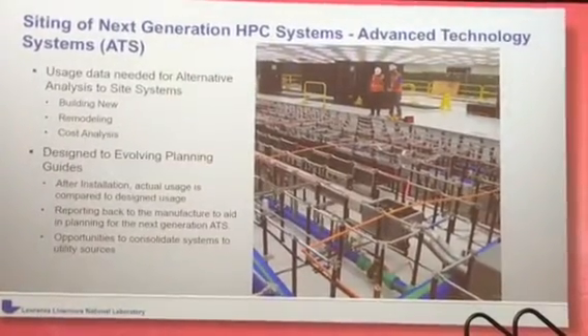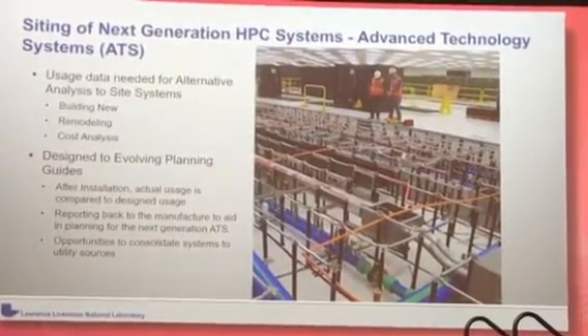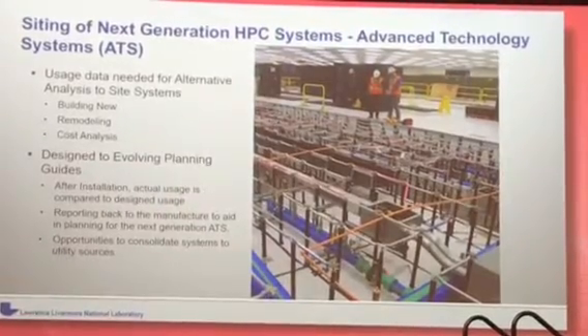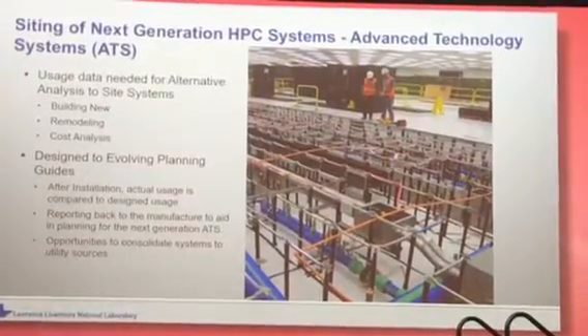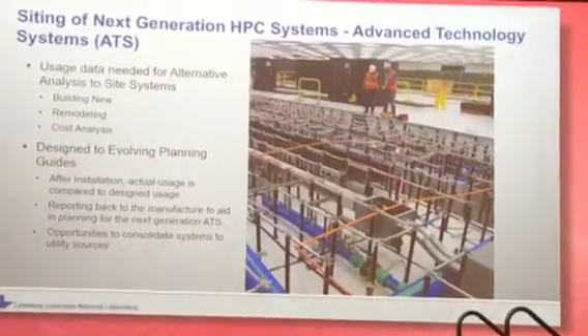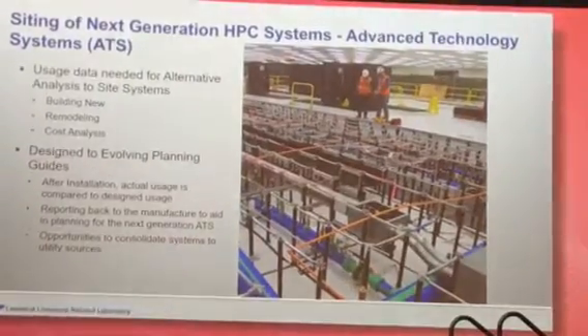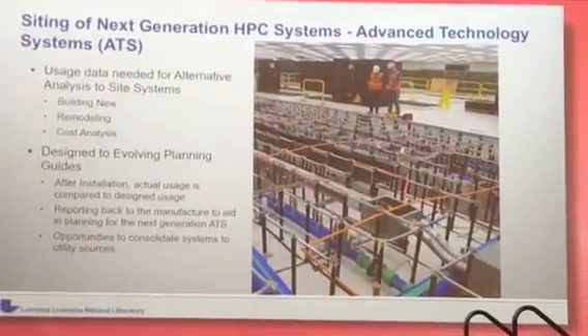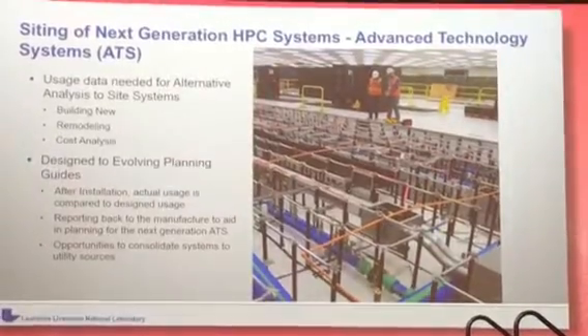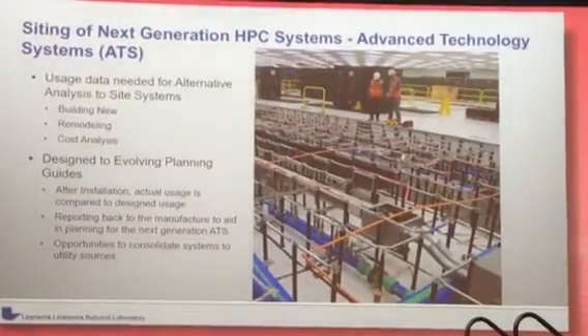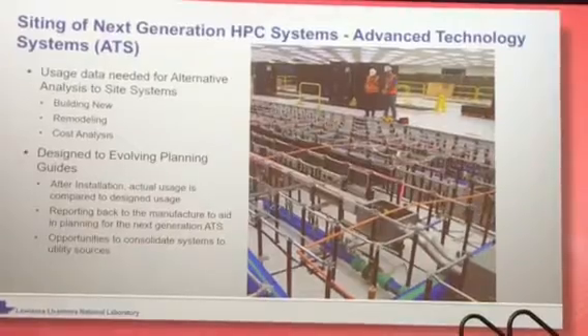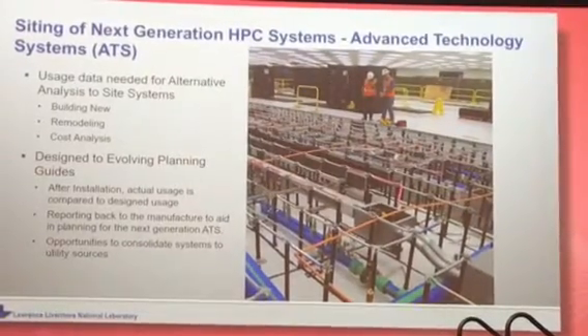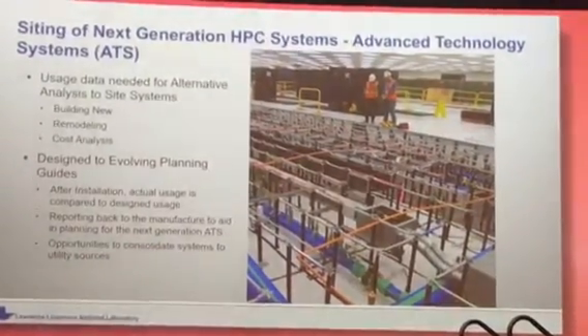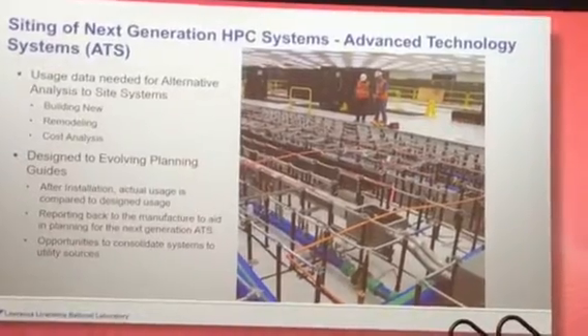One of our opportunities that we had was to consolidate some of our water-cooled solutions. Sequoia and Vulcan used to be on their own cooling loops, and we found that during normal operation those two systems could actually be on one system. And so we installed some new piping, consolidated the systems, and we had a whole vacant cooling loop for the next ATS machine.